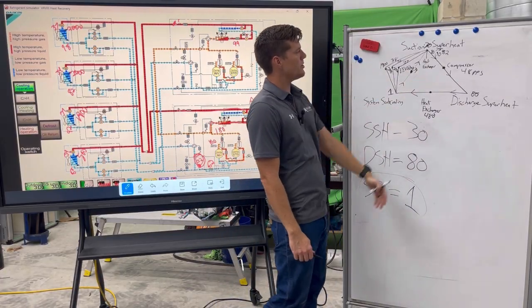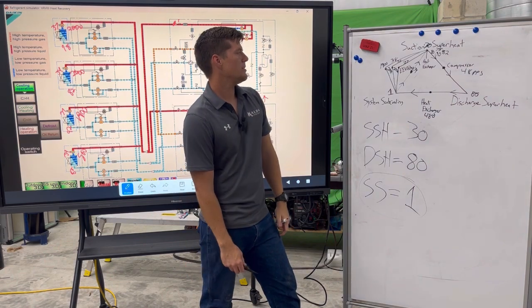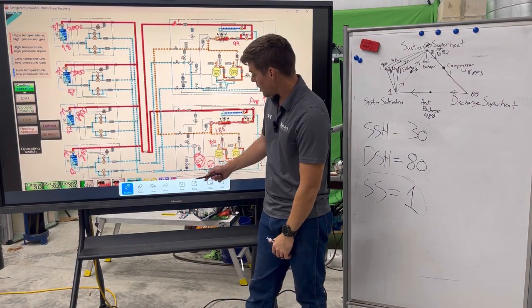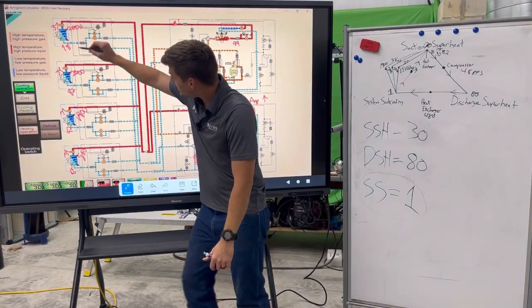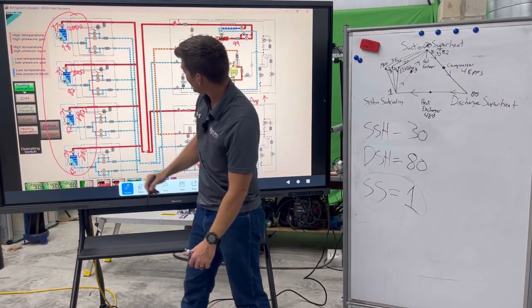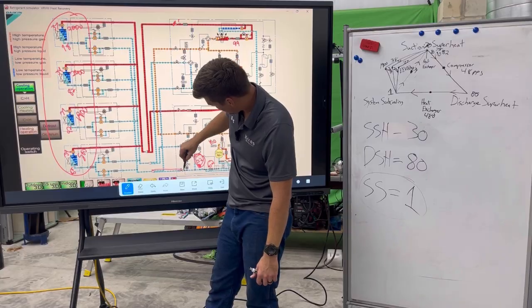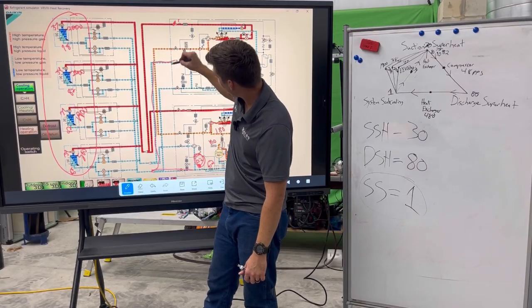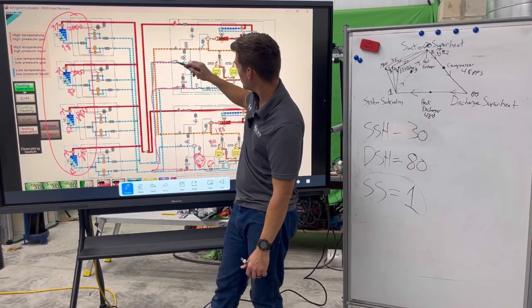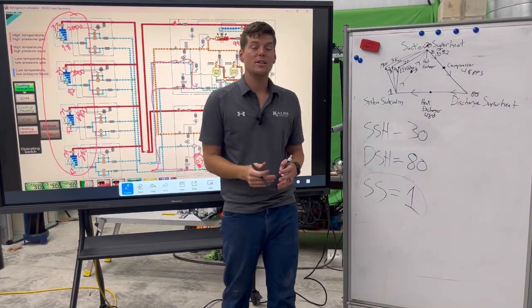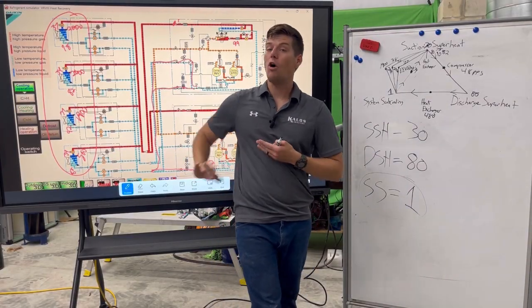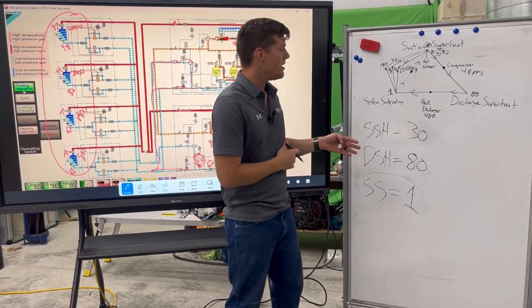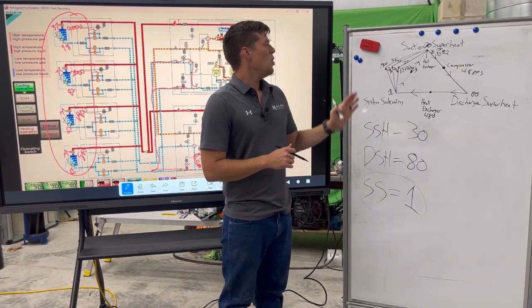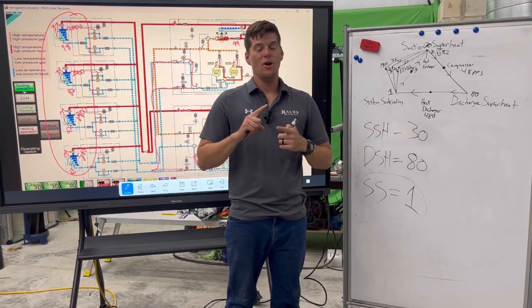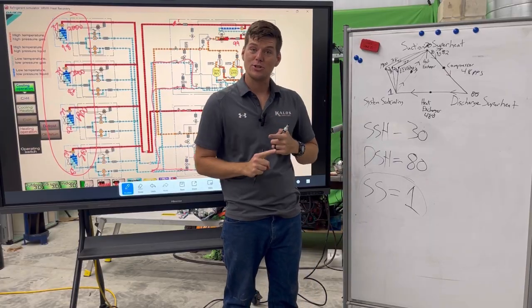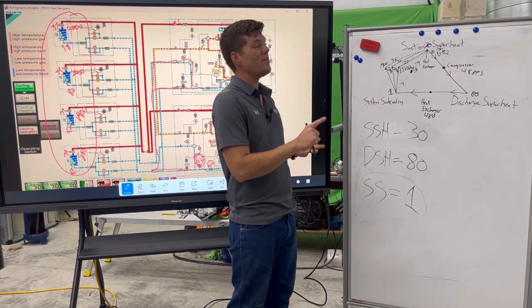And then coming back to my compressor, we already know we have a 30 degree superheat, suction superheat on my actual line. Remember, your suction superheat is all of these superheats right here combined together on your suction line back to your unit. They come together and reconnect back to your unit, all going to one line right here. So your suction superheat is basically your combined superheat for all your indoor units. That's still going to tell you the quality of vapor coming back to my compressor. Let's take a step back. We know we have a high suction superheat, we know we have an elevated discharge superheat, and we know we have a crappy subcooling.